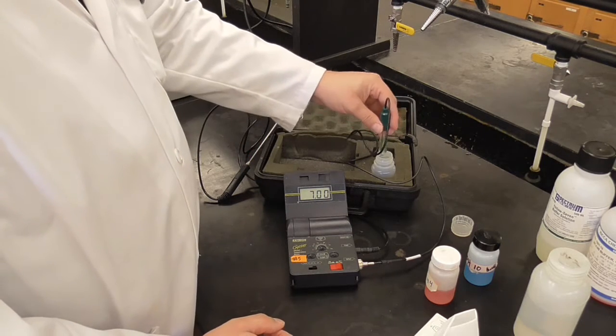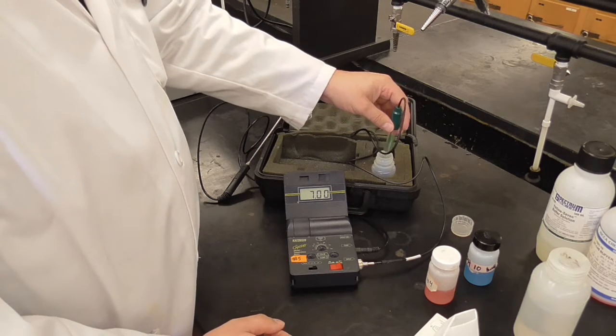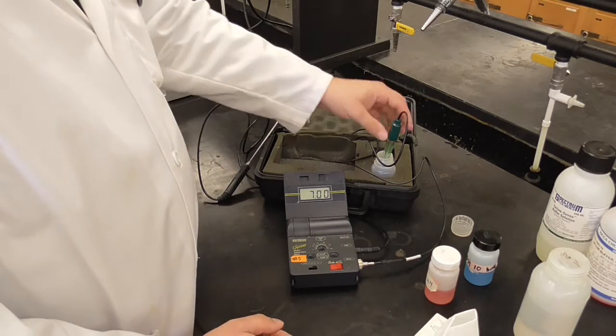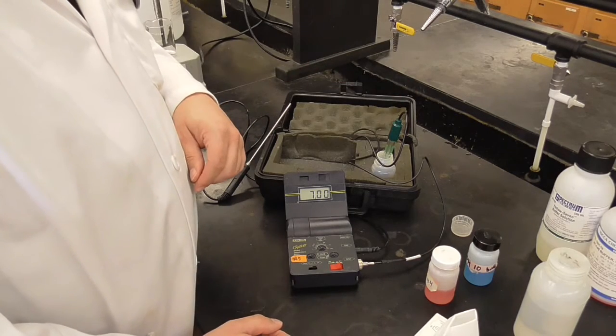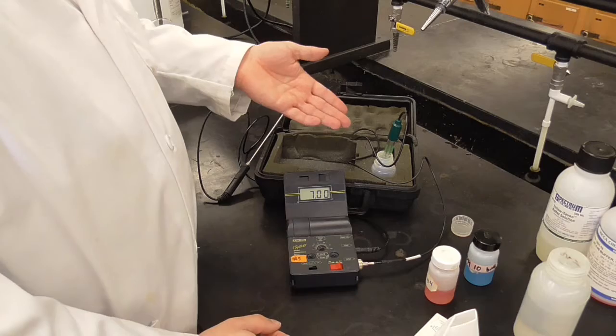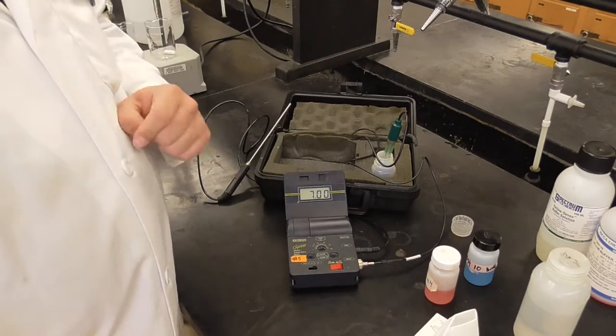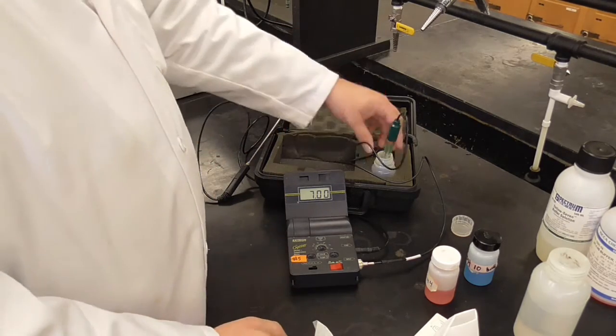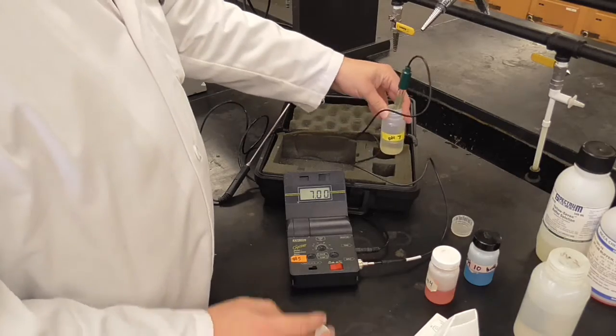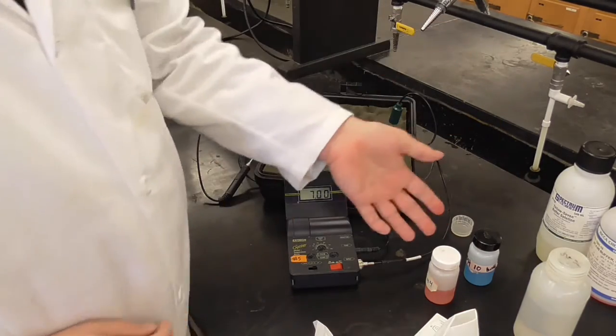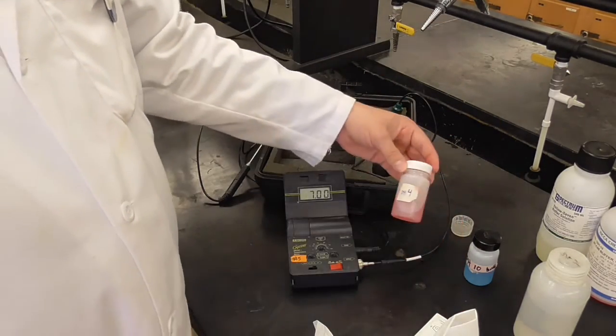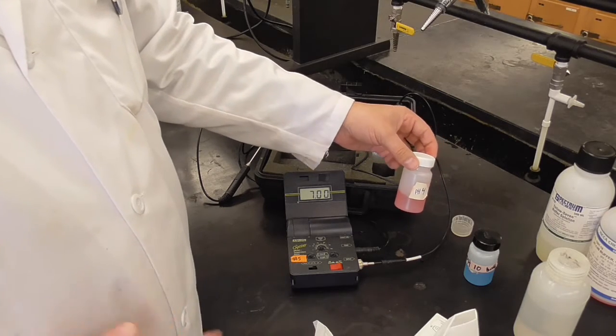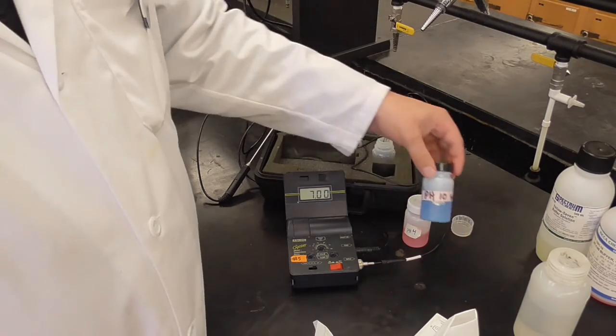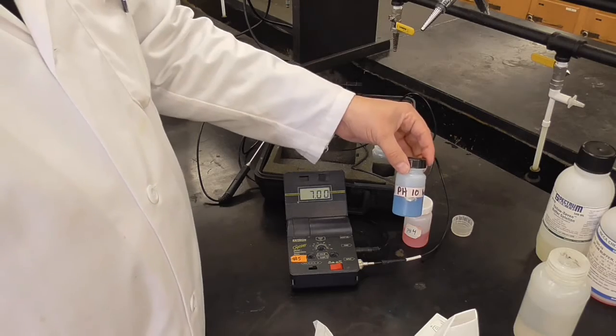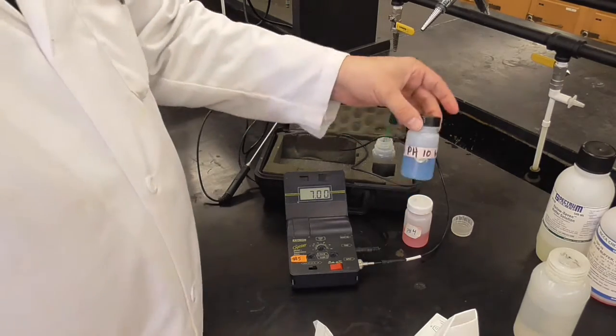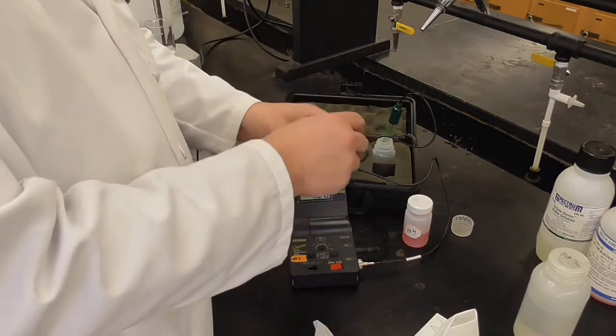Now theoretically you would put a little stir bar in there, but it's fine if you just move it around a little bit. So we've got a pH 7, that's the 1 point of the calibration. For the second point of the calibration, I repeat the process, except this time I use one of my other buffers, either the pH 4 buffer if I'm going to be doing acids, or pH 10 buffer if I'm going to be doing bases. In this case, I'm going to use the pH 10 buffer.